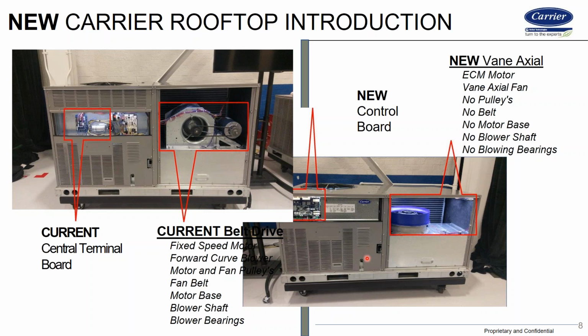So bottom line is, on every single furnace and every rooftop you put in, I don't care who the manufacturer is, you have got to hook up your magnehelic gauge and adjust your manifold gas pressure. You got to do it. Between that and the airflow and static, that will control the temperature rise part of the equation. Inlet gas pressure on these, ideally you want somewhere between 5 to 10 inches, and 7 is usually the norm. That's your inlet gas pressure to the unit. But again, your manifold pressure on high and low, you want to make sure you set those.